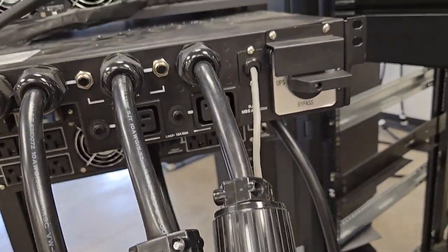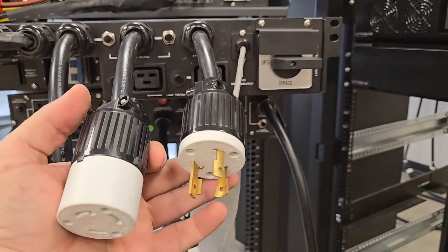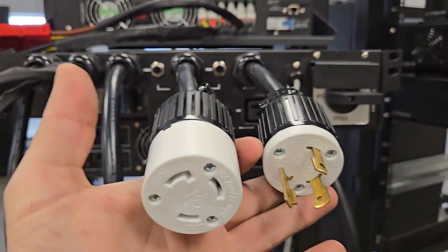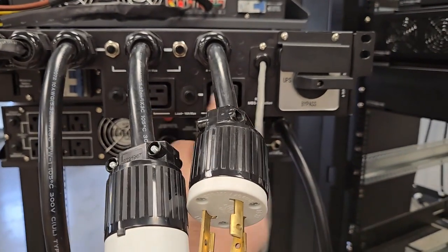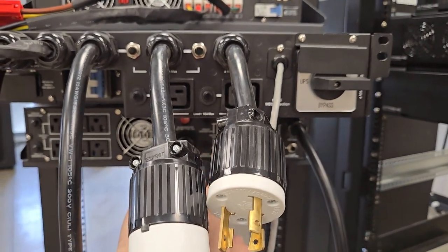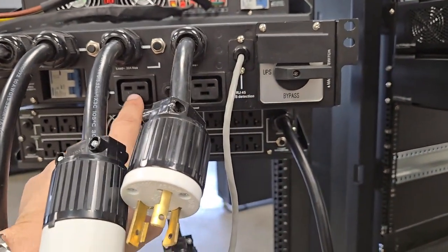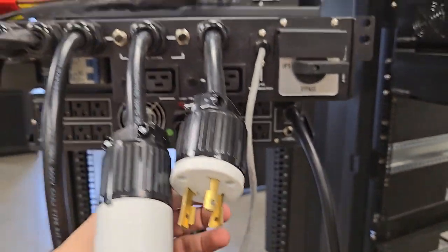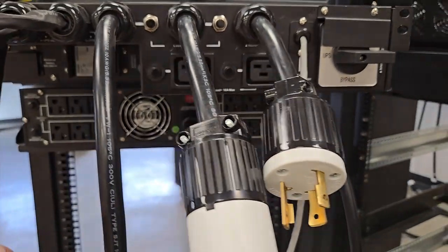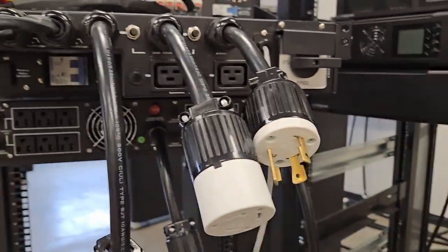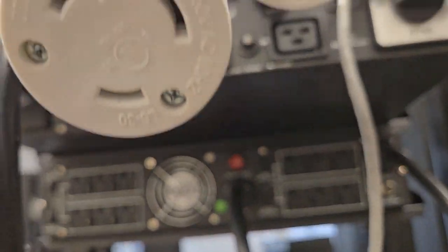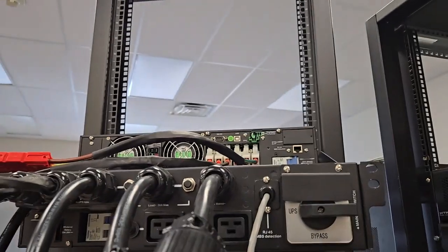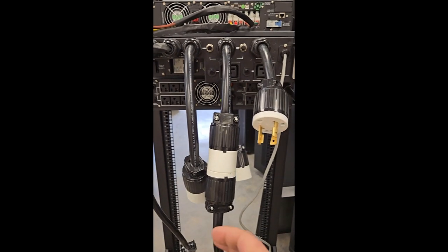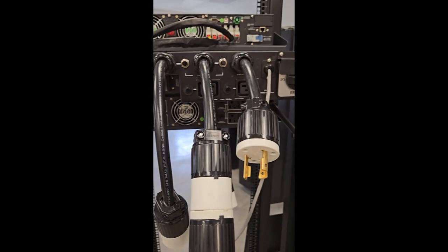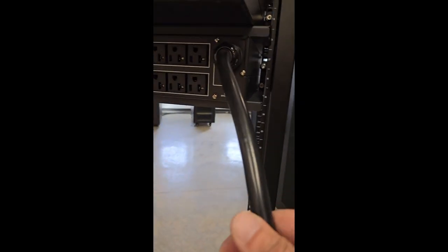Moving to the bypass input and bypass output. Here we've got optional IEC connections to plug directly in, or we connect into the transformer. I will show you how to do that here. So I've made the output connection from the bypass to the transformer module.